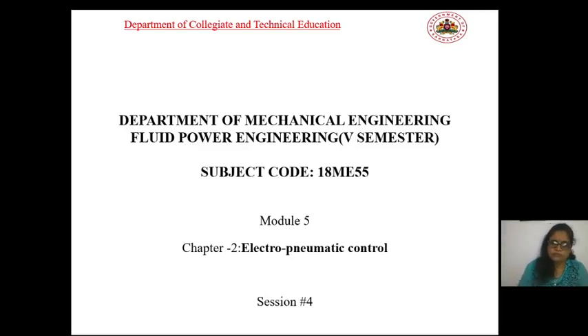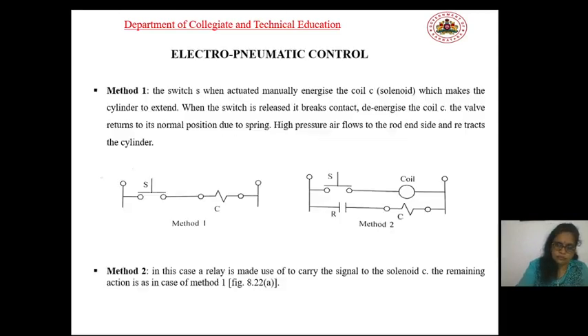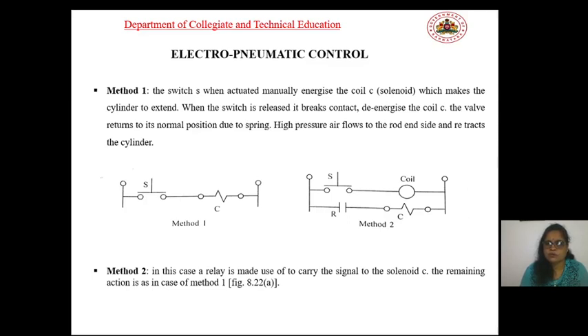Welcome to Session 4: Electro-Pneumatic Control System. In Method 1, the switch S, when activated manually, energizes the coil C, which makes the cylinder extend. When the switch is released, it breaks the contact and de-energizes the coil C. The valve returns to its normal position due to the spring, and high-pressure air flows to the rod side and retracts the cylinder.